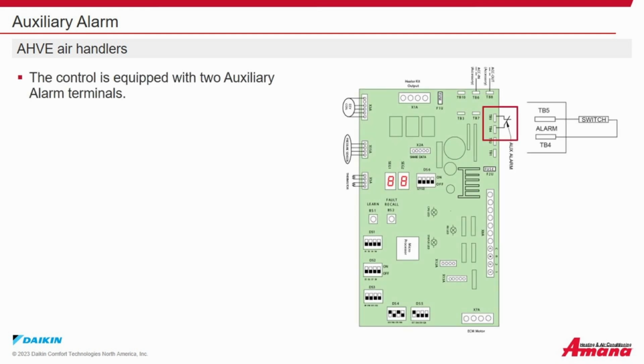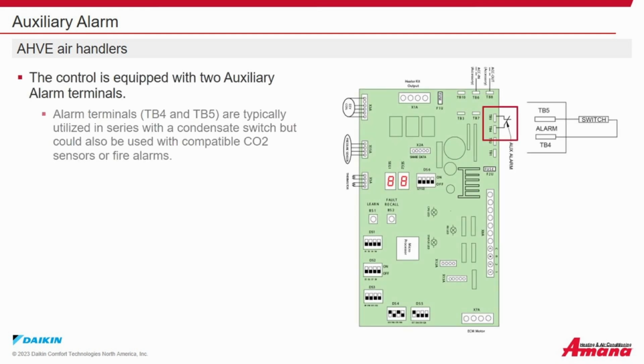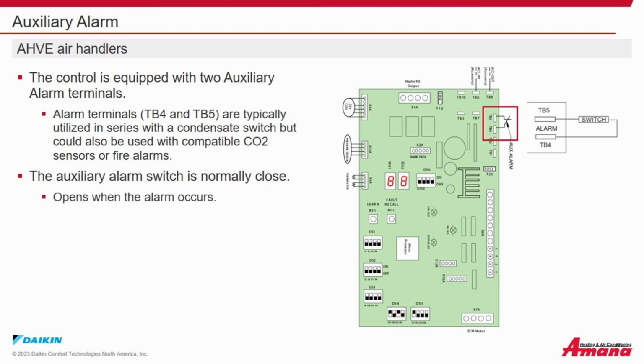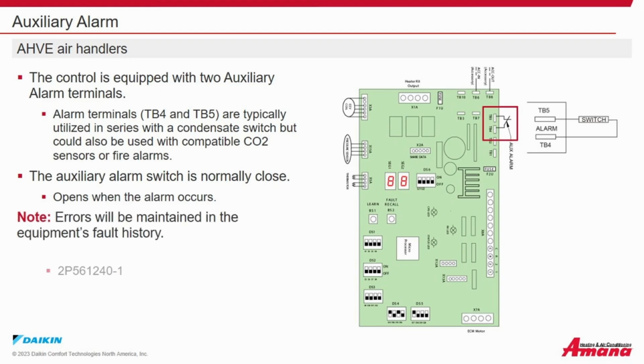Auxiliary alarm. On AHVE air handlers, the control is equipped with two auxiliary alarm terminals. Alarm terminals TB4 and TB5 are typically utilized in series with a condensate switch, but could also be used with a compatible CO2 sensor or fire alarm. The auxiliary switch is normally closed. The connections open when an alarm occurs. Errors will be maintained in the equipment's fault history. Auxiliary switch part number 2P561240-1.